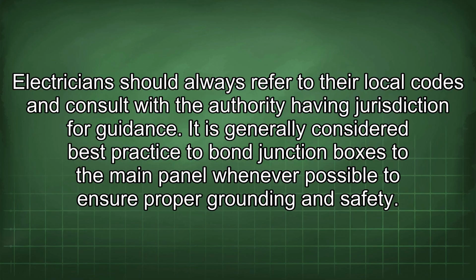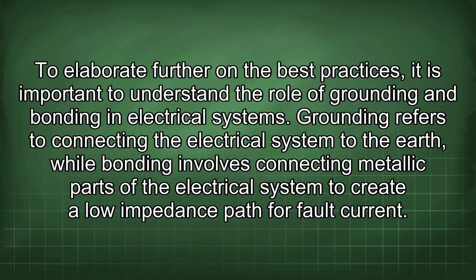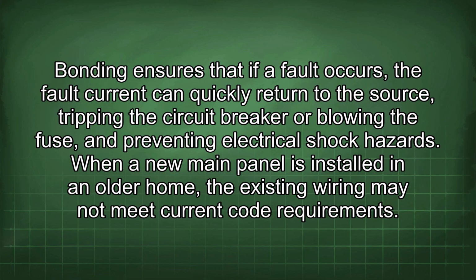To elaborate further on the best practices, it is important to understand the role of grounding and bonding in electrical systems. Grounding refers to connecting the electrical system to the earth, while bonding involves connecting metallic parts of the electrical system to create a low impedance path for fault current. Bonding ensures that if a fault occurs, the fault current can quickly return to the source, tripping the circuit breaker or blowing the fuse and preventing electrical shock hazards.